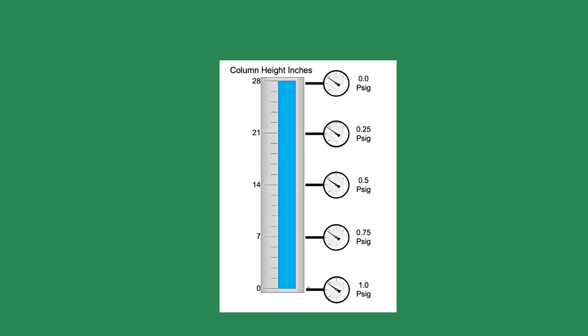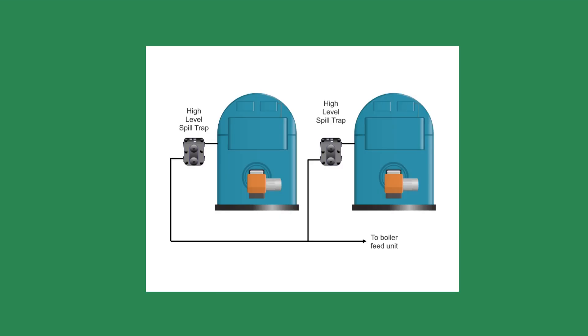The water level in the newer style steam boilers is vital and cannot tolerate wide swings in the water level. A one ounce difference between the boilers would mean a water level difference of about an inch and three quarters. That may be enough to affect the operation.